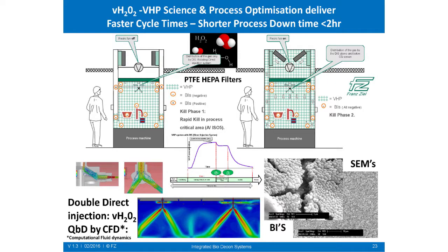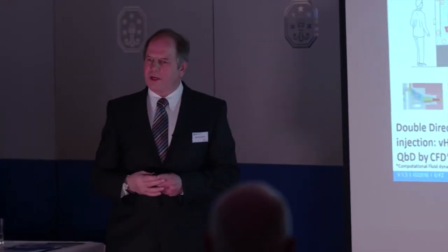It means you have classically in this phase 2 plateaus. I've emphasized it here with this longer graph. The plateau 1, kill phase 1, change the injection rates, get the recirc fan going, plateau 2, and then your classical exponential reduction.